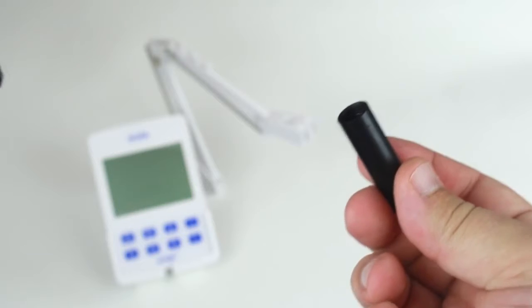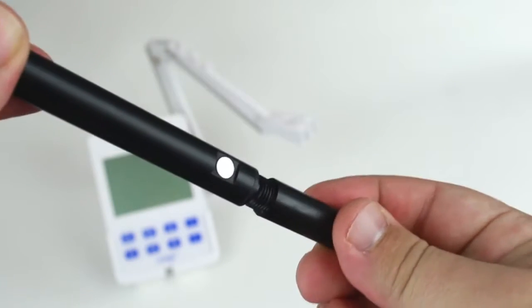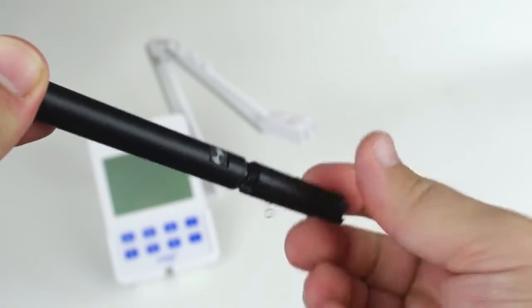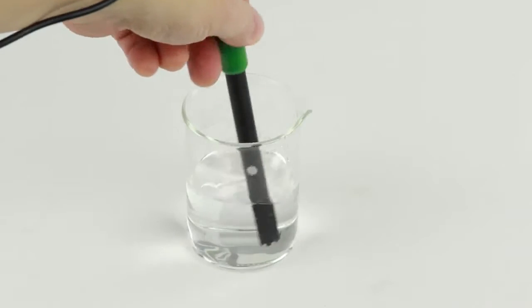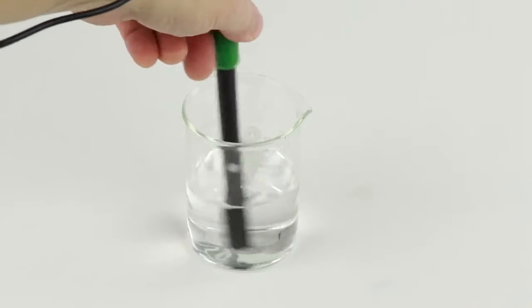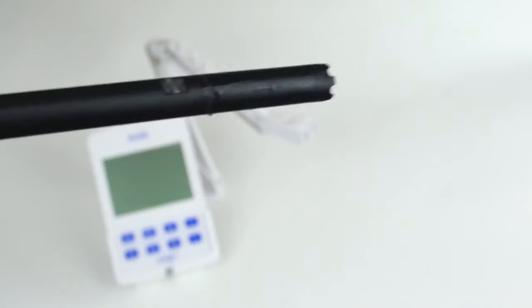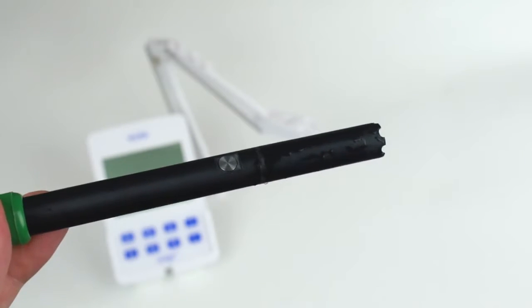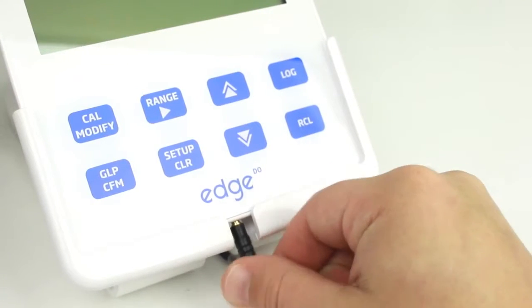Once there are no air bubbles, screw the cap onto the probe. Some electrolyte will spill out. This is normal. Then, rinse the probe after filling. The probe is now fully assembled. Inspect the bottom of the probe for air bubbles. If there aren't any, simply connect the probe to the meter and turn it on.